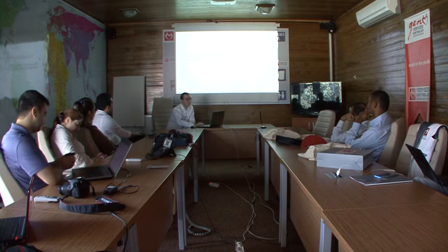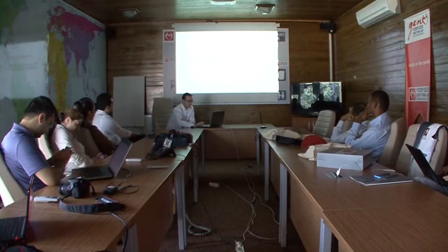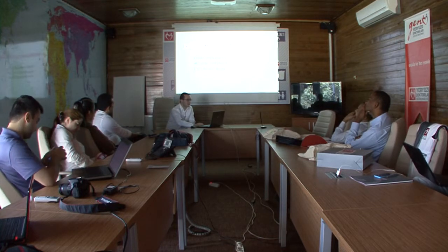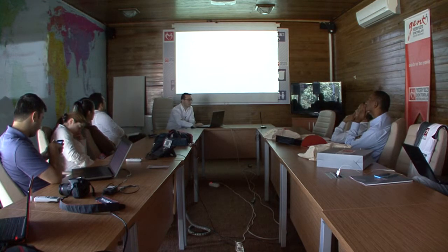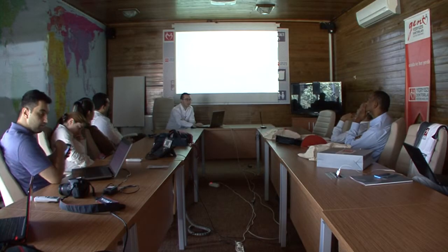After the setup, we can start the test by pushing only one button on the computer. During the procedure, we may experience some problems such as high impedance, muscle artifacts, or electrical noise. Electrode impedances must be in the range of 1,000 to 5,000 ohms; values greater than 5,000 indicate high impedance, meaning the contact between the electrode and skin is weak. In such a case, the skin cleaning procedure must be repeated or the electrode placement areas may be changed.